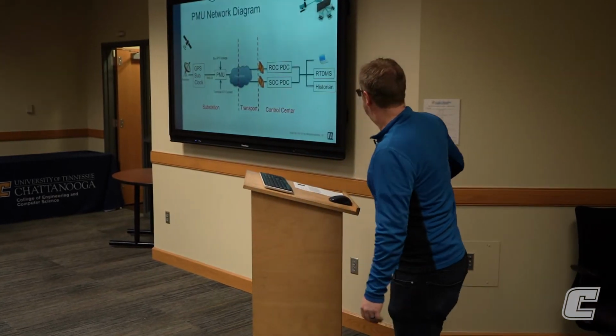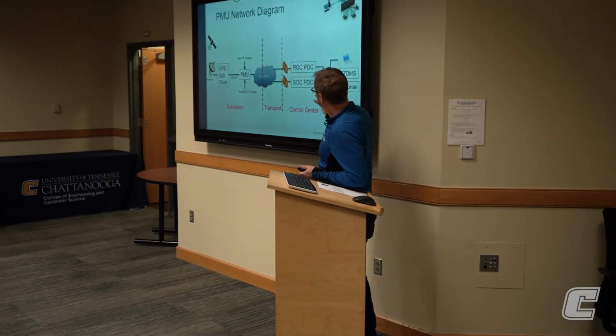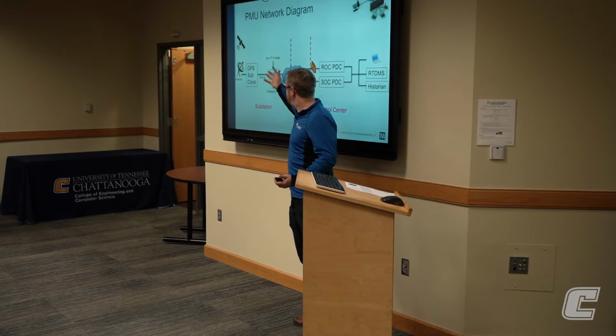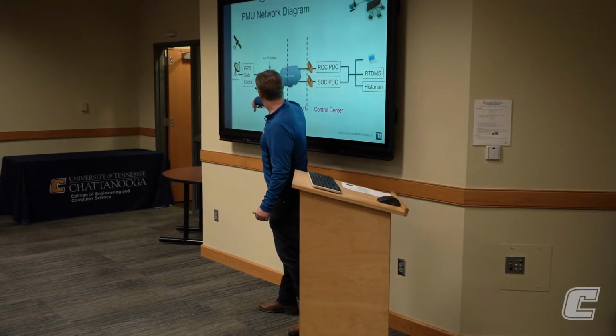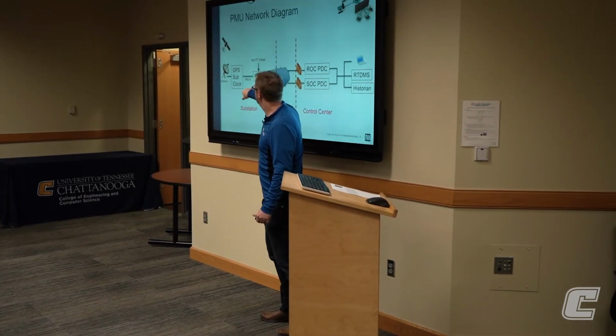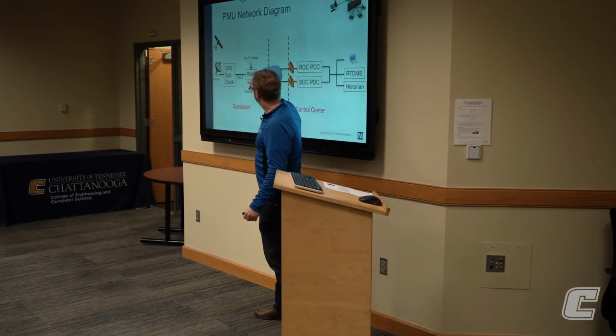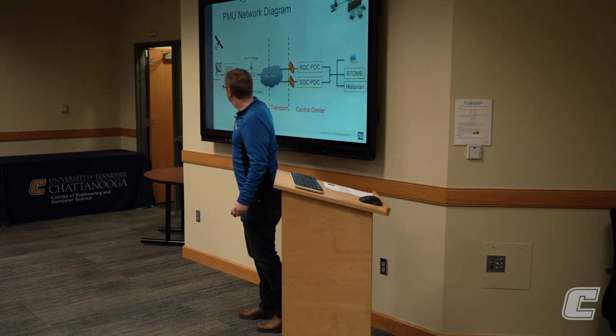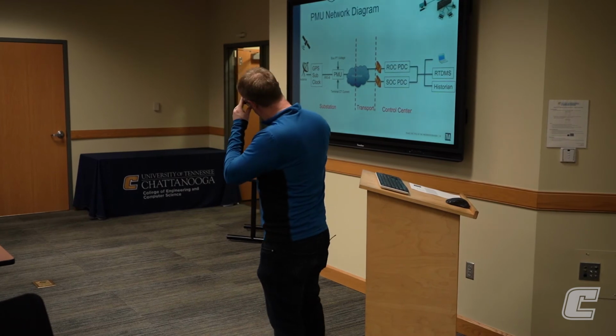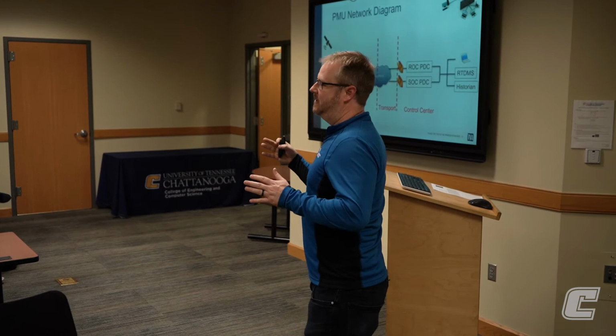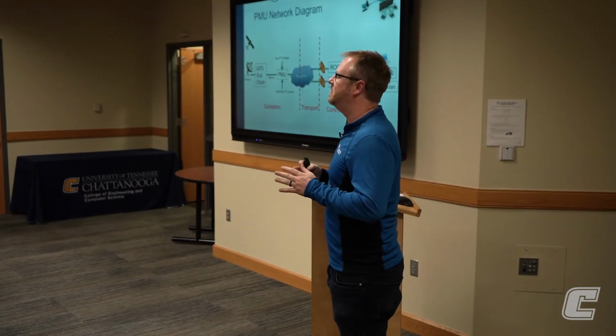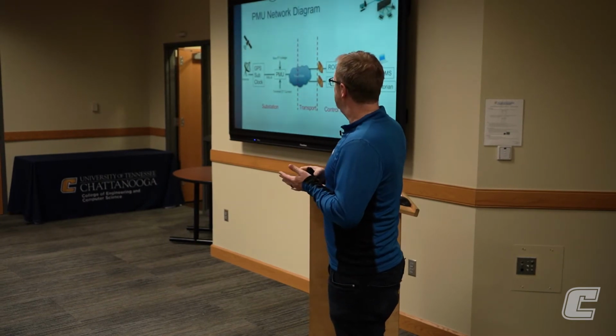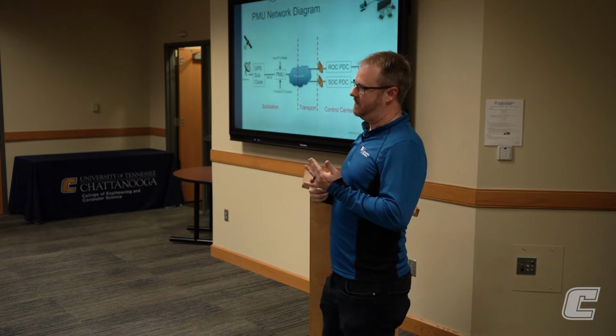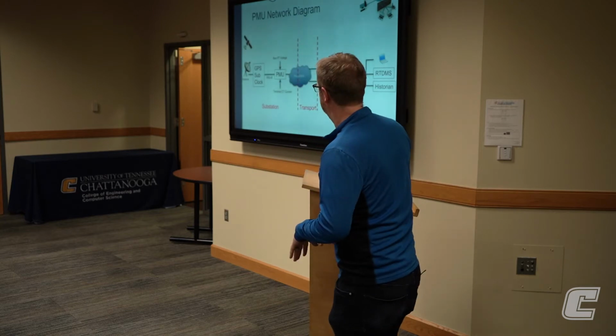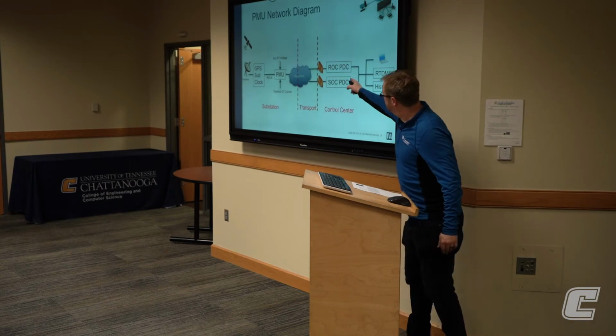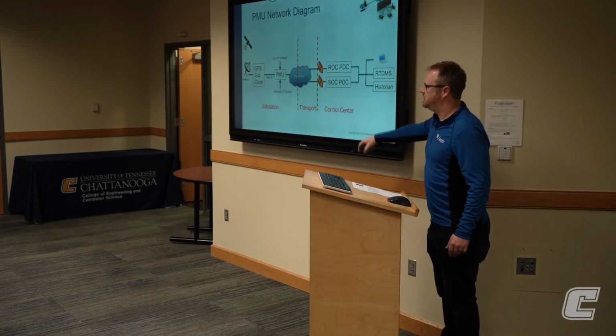This is a high-level diagram of how it works. You've got a box, the PMU device, like a laptop in a box. It has current and voltage from a substation feeding into the box, from a potential transformer and a current transformer. Remember how important the timestamp is: we have a GPS clock at each substation that provides a high-resolution timestamp, feeding into the PMU as well. So three things feed into the PMU device: a current phasor, a voltage phasor, and a time clock signal from the GPS clock. That all goes across a network into our control centers at TVA, and then into our end users, which we'll see later. RTDMS is our real-time dynamic monitoring system.